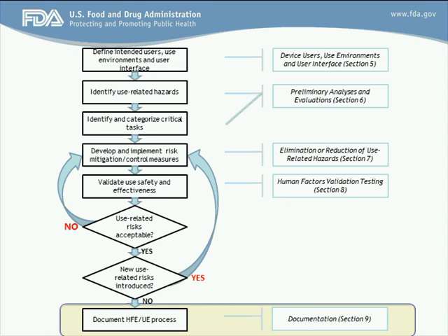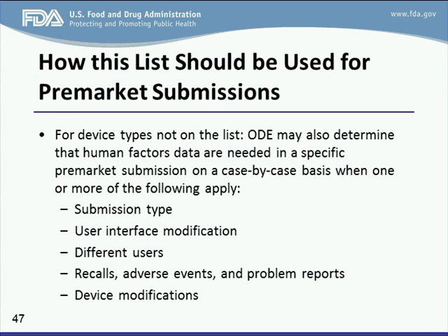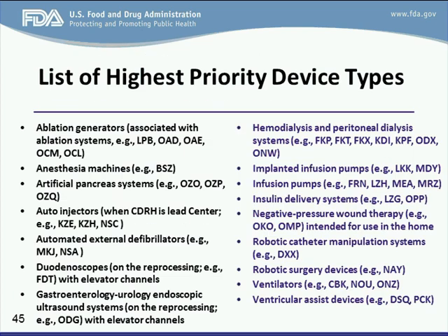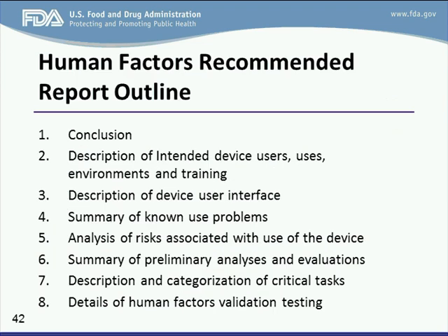Mr. Trum? Oh, yes. At the last slide, I think you mentioned submitting protocols to the agency for review. Is that for both summative and formative? It's for summative. It's only for summative. Formative protocols are not allowed to be submitted, because we are only going to basically concentrate on your human factors validation testing or usability validation testing. Okay, thank you.